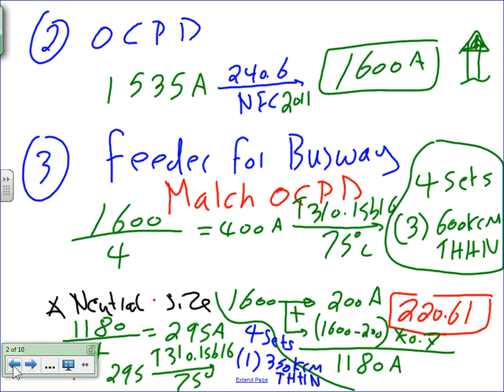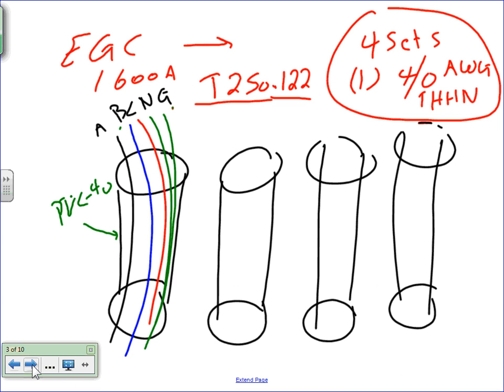So you're feeding a 4-inch pipe into a 3-inch pipe? No, they're not tying together, as in pipes. Where does it run? Doesn't it all eventually go to the grounding electrode conductor? Yeah. But the reason why this came up to be a big boy, the 4-aught, is because we're paralleling. I see your point, though. But when you go to the grounding electrode system, just FYI, you wouldn't find only 3-aught. You'll find multiple 3-aughts because we tie to the water line, we tie to the ground rod, we tie to the steel.